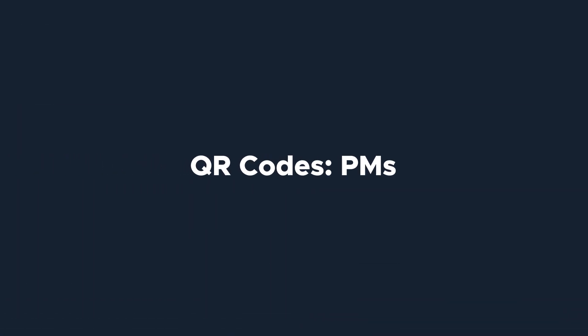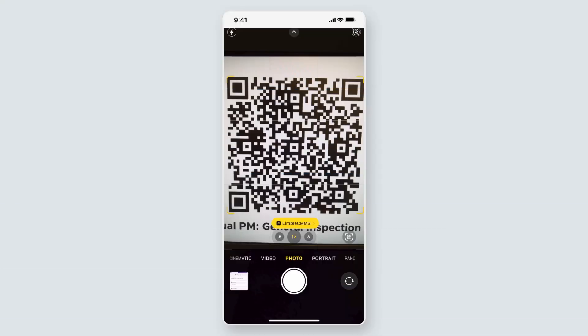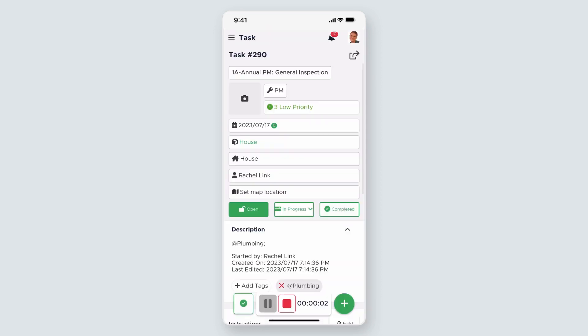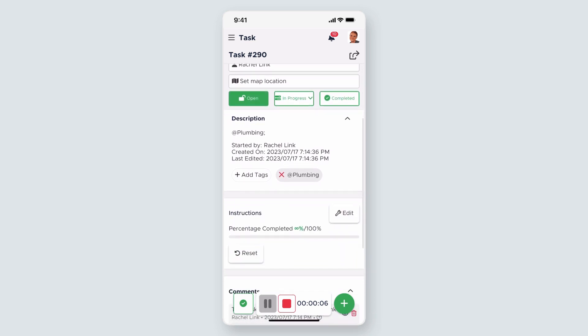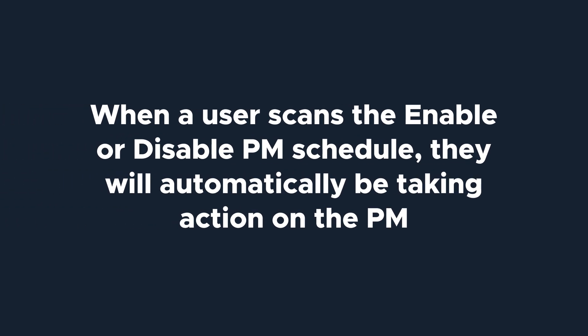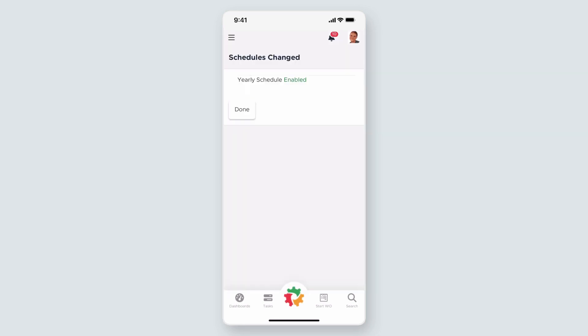Let's switch gears to look at tasks, starting with PMs. PMs have two QR code options: one to start a task and another to enable or disable the PM schedule. When a user scans the start task QR code, Limble will check to see if the task is already open and in progress. If it's already open, scanning the QR code will automatically take the user to the task. If the task is not open, scanning the QR code will open a new task and the user can begin work on it right away. When a user scans the enable or disable PM schedule, they will automatically be taking action on the PM. If the schedule is enabled, scanning the QR code will turn off the schedule and the PMs will no longer generate. If the schedule is disabled, scanning the QR code will turn on the schedule and the PMs will begin to generate again.